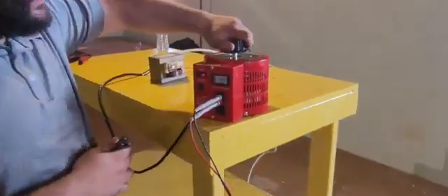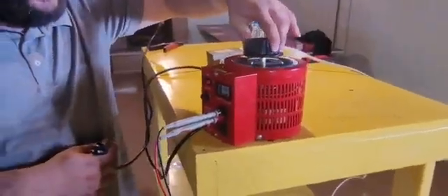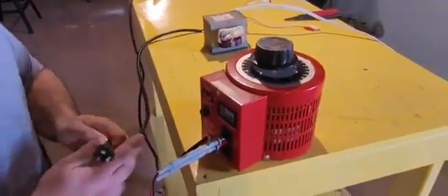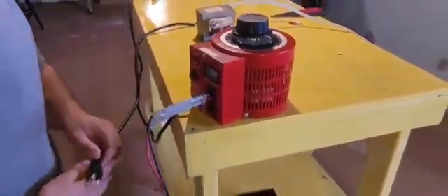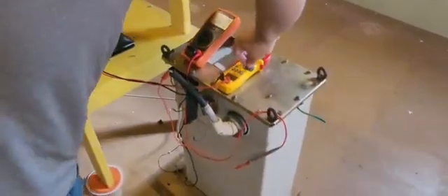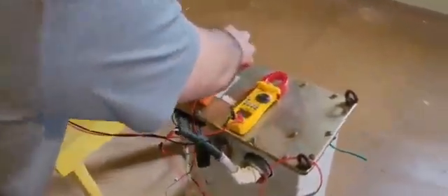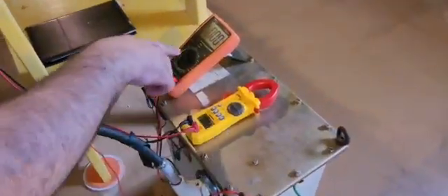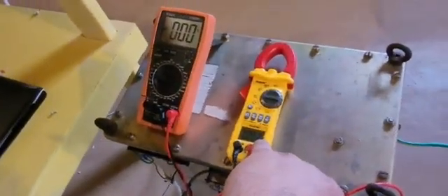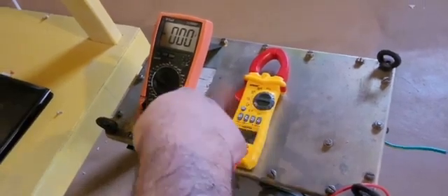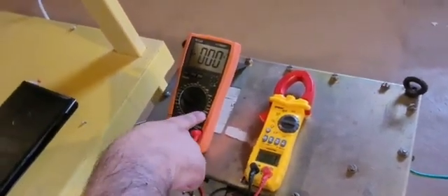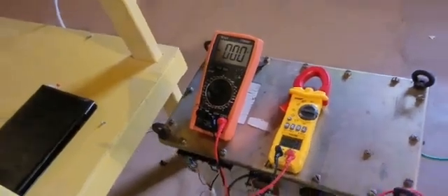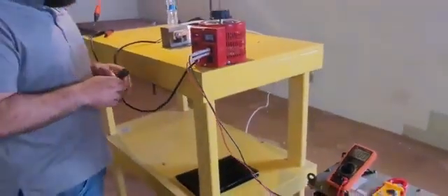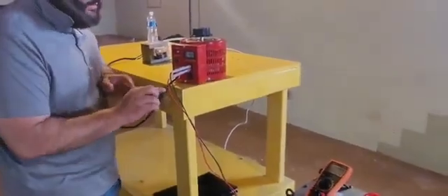I'm just using standard 120, but for this test, you see I have the variac cranked all the way down to 0, and the residual voltages in the variac make it not perfectly 0. I'm going to reset these meters just to make sure they don't die on me. This meter is measuring voltage AC coming from the variac. You can see it's almost nothing, which is good. Just the residual voltage in the atmosphere is what it's picking up. This one is set to 1,000 volts DC. For this test, we will not be going over 1,000 because I really do not want to damage my meter.